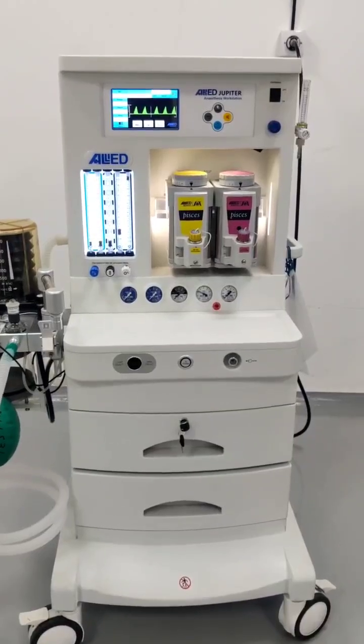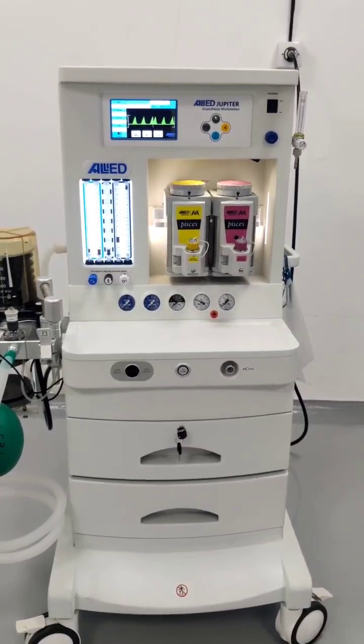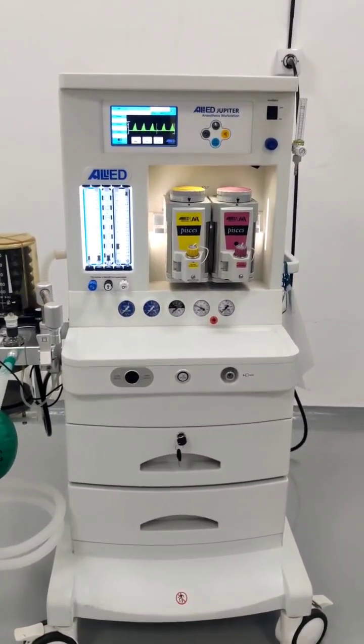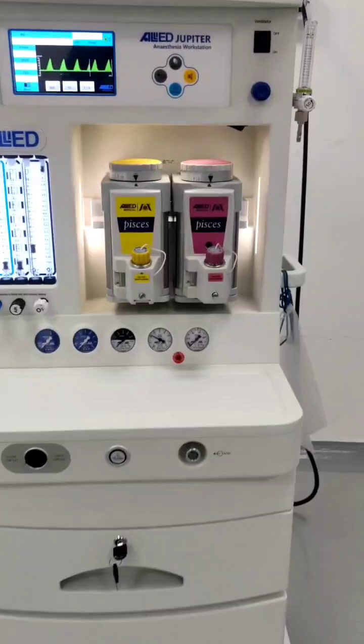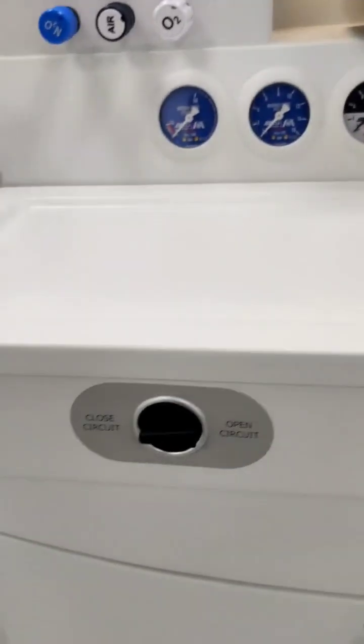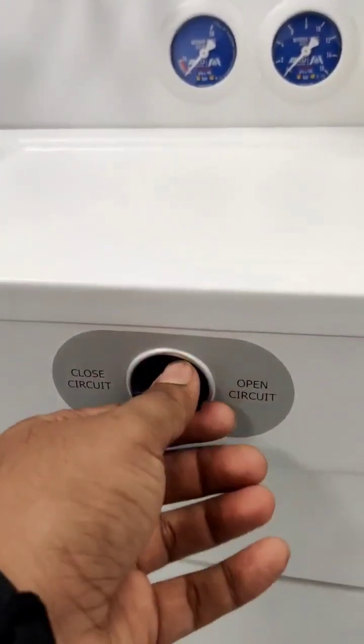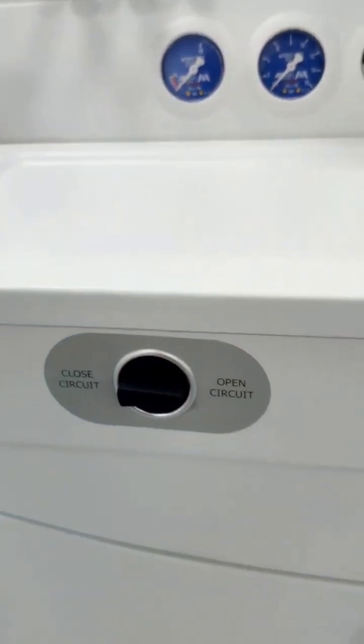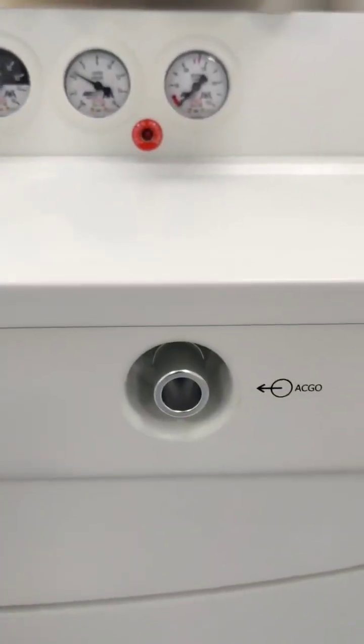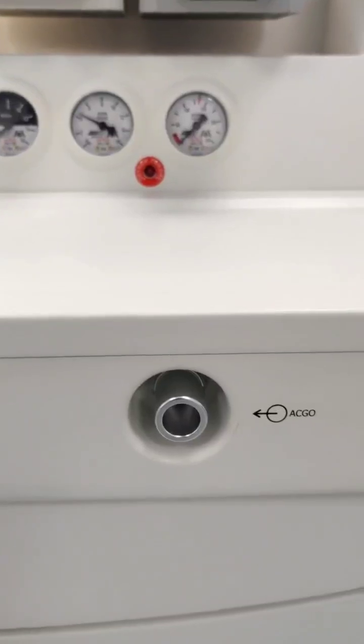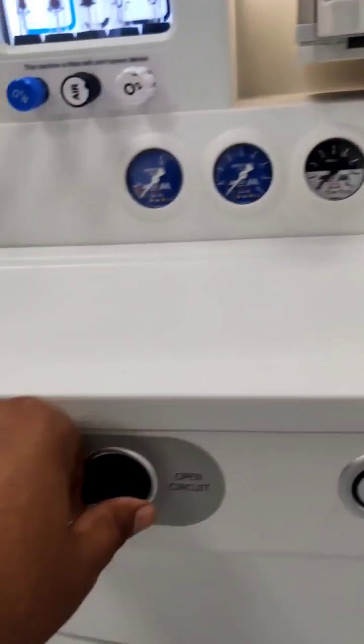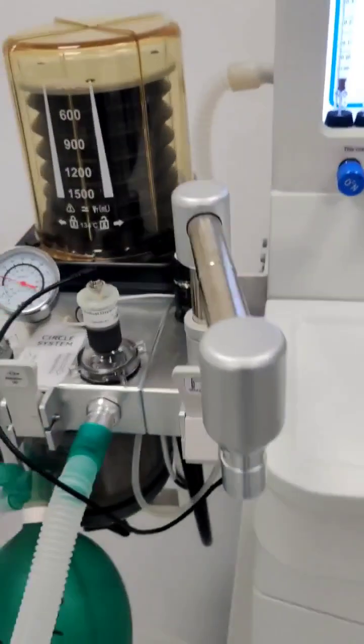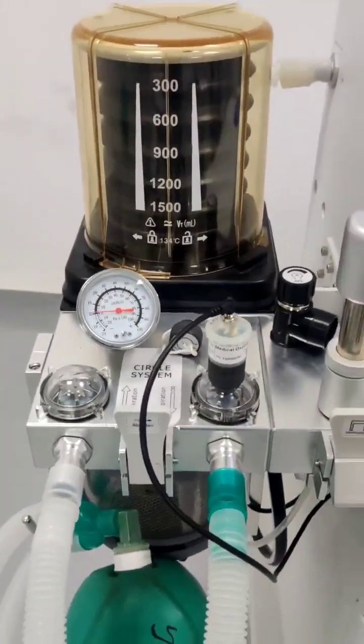The anesthesia workstation can be operated on two circuits. One is the open circuit and the other is the closed circuit. This one is the open circuit over here. The changeover you can do from here with the help of this knob. On the open circuit you will be getting the output from the ACGO, that is the auxiliary common gas outlet, and on the closed circuit the gases will be going to the circle absorber system.